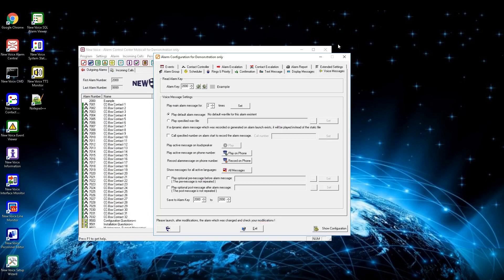In the voice message settings window you can define what voice messages are sent at the alarm call. The voice file must be in 16-bit, 8 kHz, mono WAV format. The first option adjusts how often the voice message shall be repeated — two times by default. A default alarm message can be set; by default there is none, so MobiCall uses a message saying the alarm has been launched with no action needed. If there is a file in the folder D:\dbv1 with the format v[alarm number]_1.wav, MobiCall will use that message for the corresponding alarm.